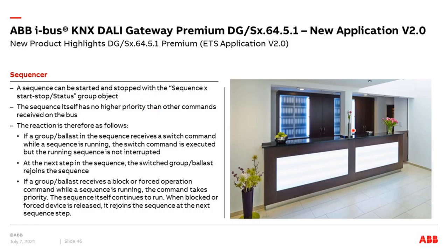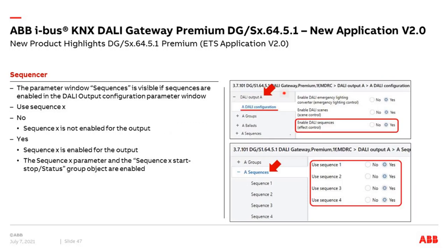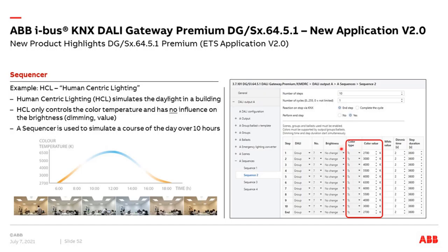A typical application is in a hotel lobby where colors change slowly between red, green, blue, and purple. To activate sequences in the ETS, you go to the main menu, Output A, Configuration, and then activate sequences — yes or no — just as you do for scenes, emergency light converters, groups, or individual ballasts. If you enable sequences, you find the four sequencers and can enable all four, or just one, two, or three.